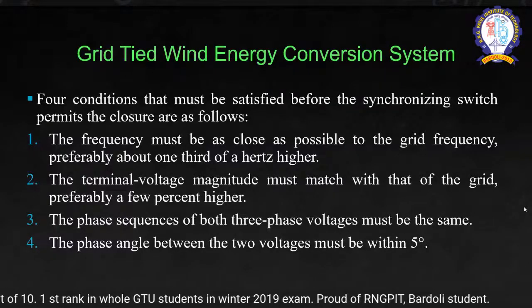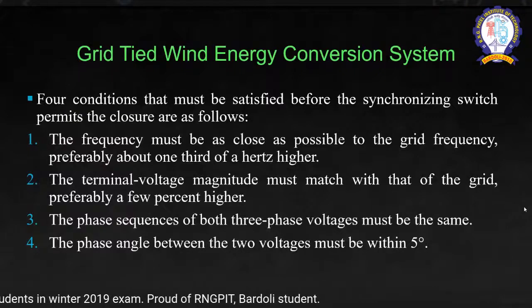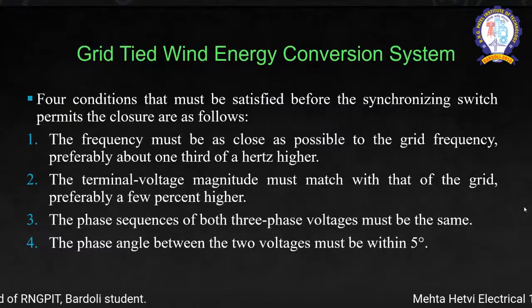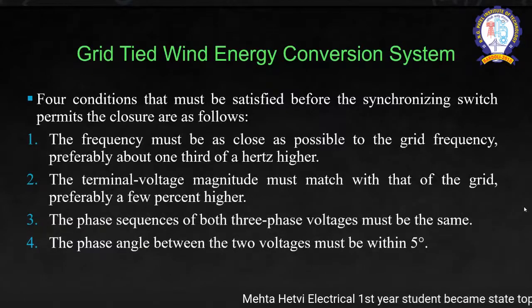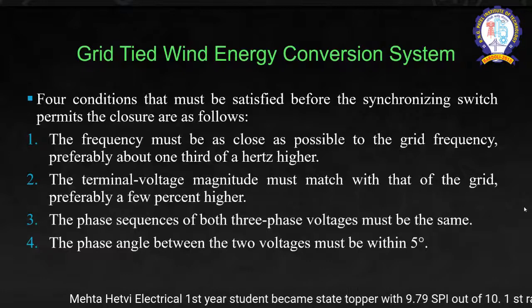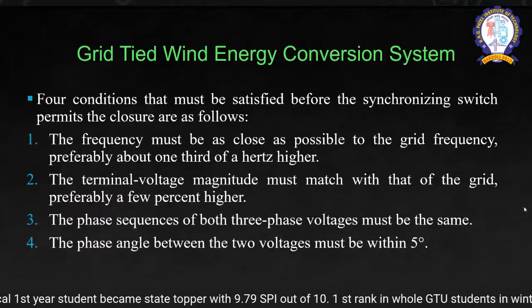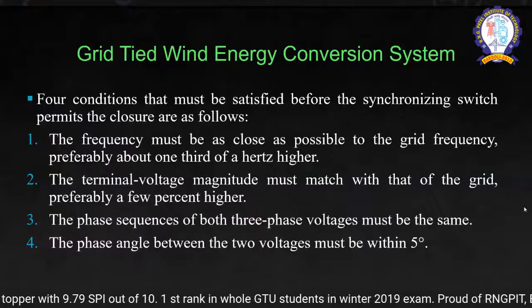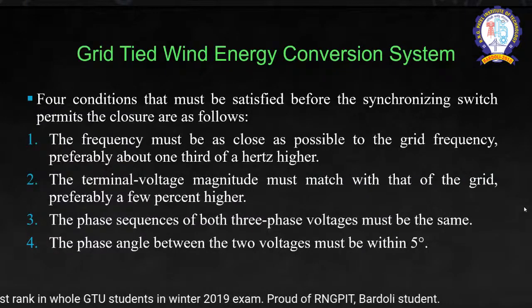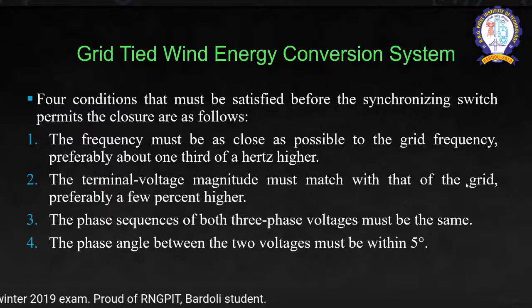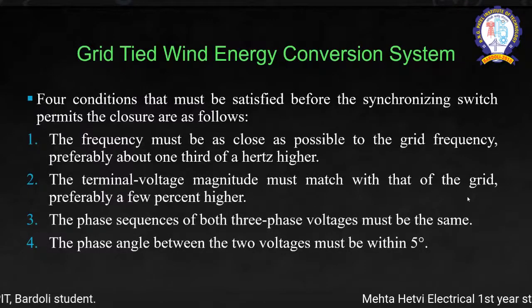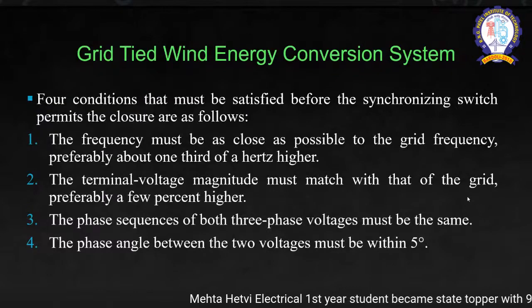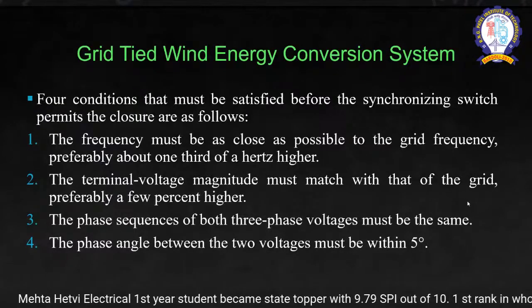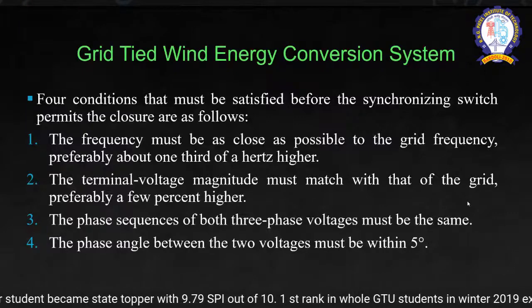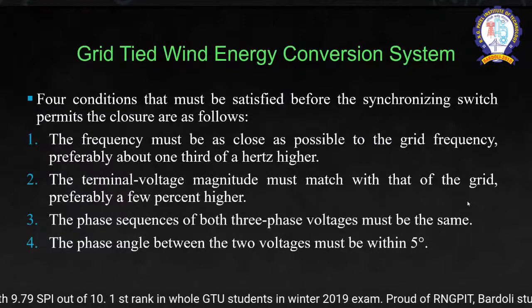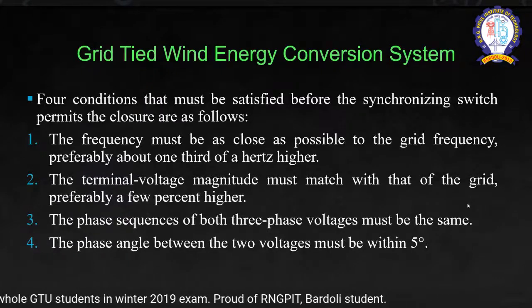Now, in the case of the frequency limit, we have a band of 1 hertz, that is 49.5 hertz lower and 50.5 hertz upper. Within that band, we need to integrate this wind farm. The frequency must be as close as possible to the grid frequency, preferably 1/3 of a hertz higher, because we need to push the power into the grid. The terminal voltage must match the grid voltage, preferably a few percent higher, so you can pump the electrons into the grid.